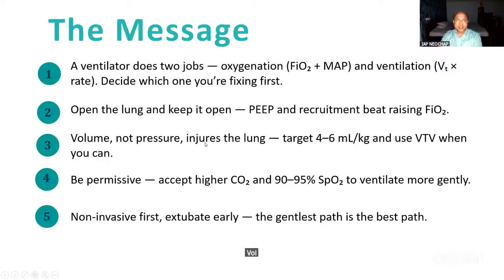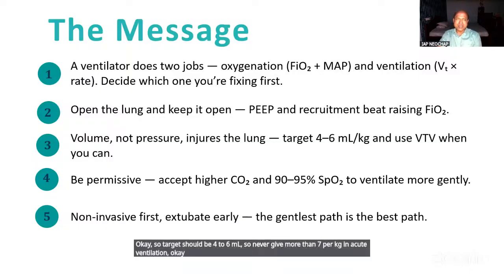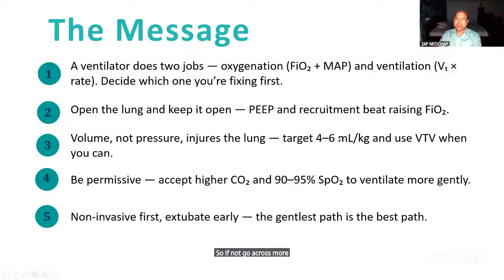Volume is injurious to the lung, not pressure that much. So the target should be 4 to 6 ml per kg. You should never give more than 7 ml per kg in acute ventilation. In chronic ventilation, sometimes we go to 7, 8, 9 ml also, like CLD babies. But for acute ventilation, should not cross more than 7. So 4 to 6 is the target usually. Be permissive: if your pH is all right, more than 7.2 or 7.25, accept higher CO2, especially in chronically ventilated babies.